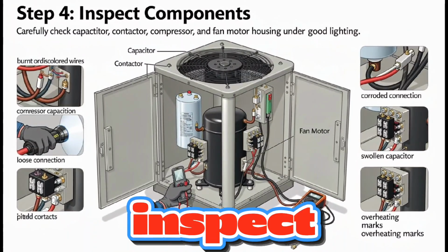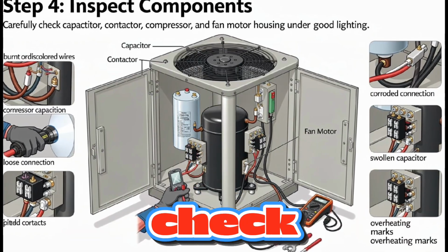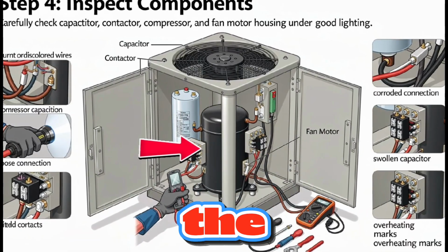Step 4: Inspect components. Now inspect key components. Check the capacitor. Check the contactor. Inspect the compressor and fan motor. Look for burnt wires, loose connections, or damaged parts.